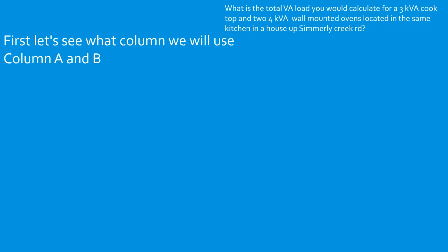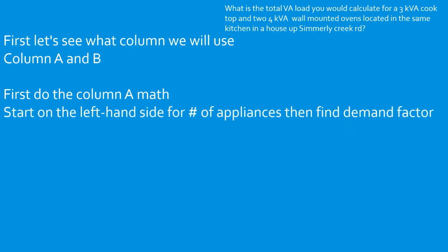Now this is very simple. What you do is apply the individual demand factors and then just add the total together. So let's start with our column A math. Our first range falls in column A. So we start on the left-hand side for our number of appliances, and then we slide over to column A, and we find our demand factor. In this case, we find that it's 80%. So we take our column A range, which is 3,000, multiplied by 0.80, and that's going to give us 2,400. Now we're done for that part.